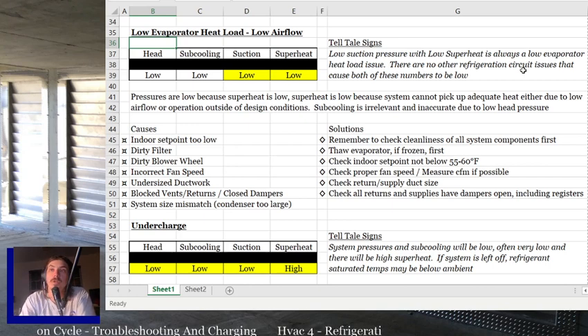Because if you're just low on charge, you should have high superheat. You shouldn't start freezing. If you're just low airflow, but your charge is good, a lot of times the suction line will still end up staying above freezing long enough that it'll cycle a little bit or something will happen and it won't turn into a block of ice. So just keep it in mind. Always check for both when you have a completely frozen coil.